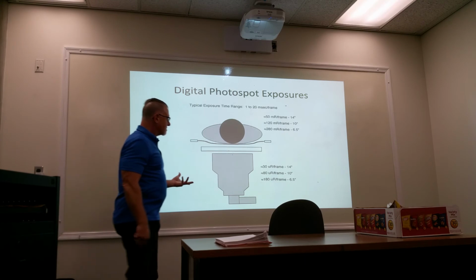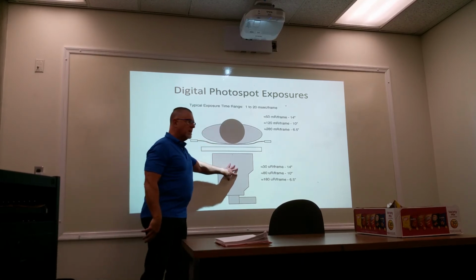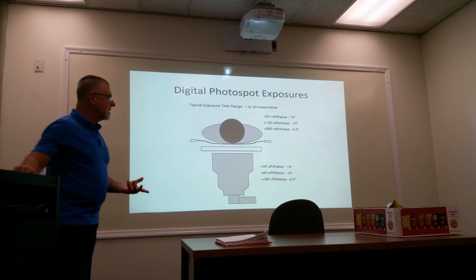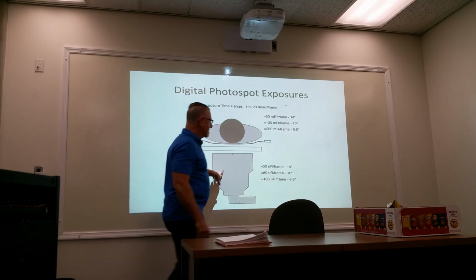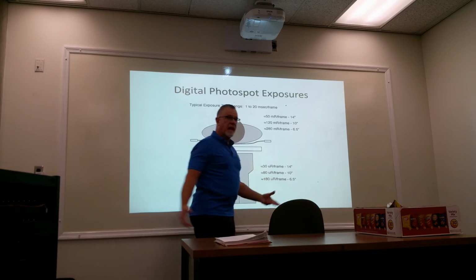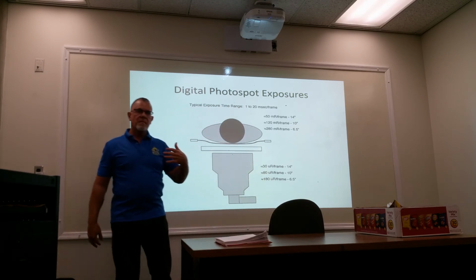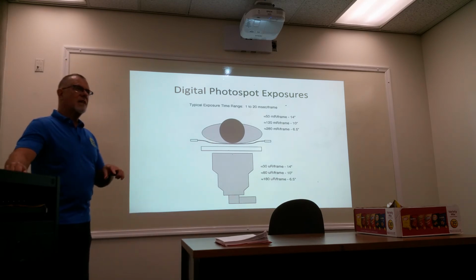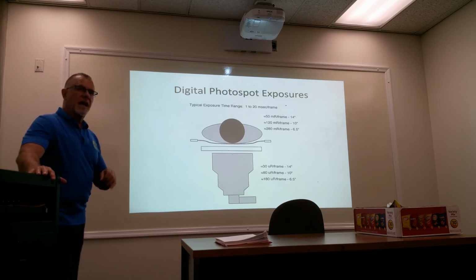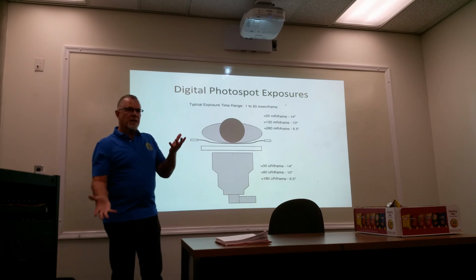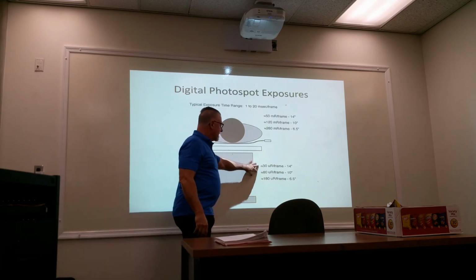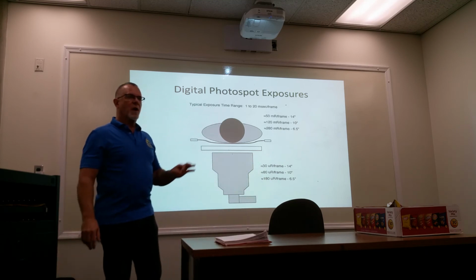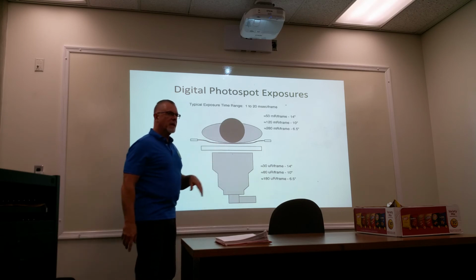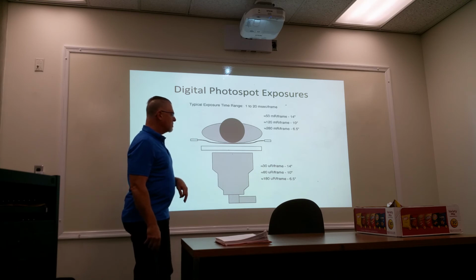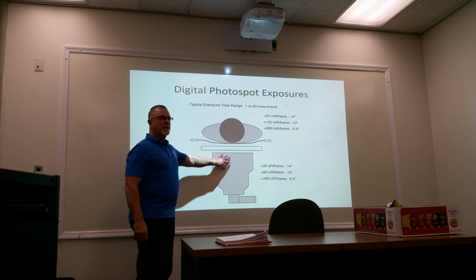Digital photo spots. To figure out what the patient gets, you need to know what the image intensifier and the optical system is set for. Typically, this is a 14-inch fluoro, so it's 14, 10, 6.5. In order to get a level of noise that is sufficient for good image quality and yet not overly so, you're trading off image quality noise versus patient exposure. The manufacturer for this particular unit sets that up to about 30 microR per frame. So that means every time an image hits this, it's about 30 microR. 80 microR in 10-inch mode, which is more than twice. 180 microR per frame when you drop down to 6-inch mode. So that's what the image intensifier needs.